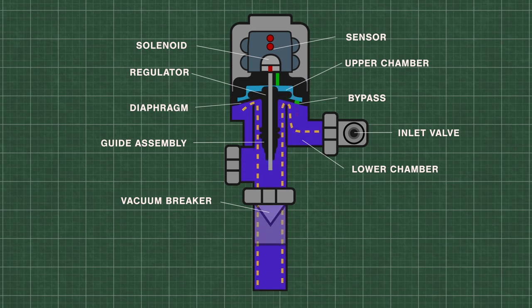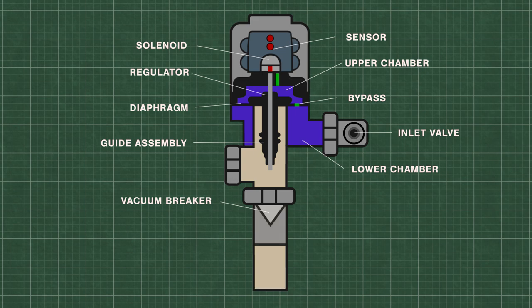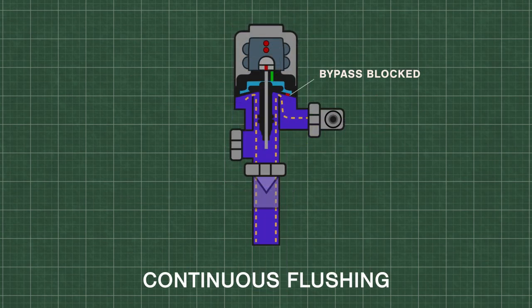During the flush, some of the water is forced back into the upper chamber through a small bypass hole in the diaphragm. The flush continues until the pressure equalizes and pushes the diaphragm down onto the valve seat. The bypass hole size is extremely important for proper metering of water. Continuous flushing can happen when the bypass is clogged with dirt or debris.